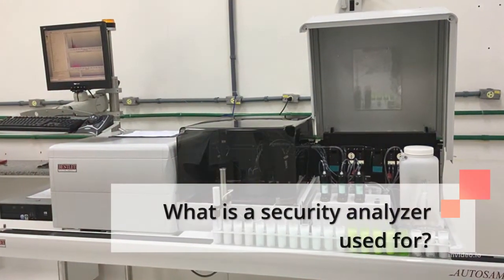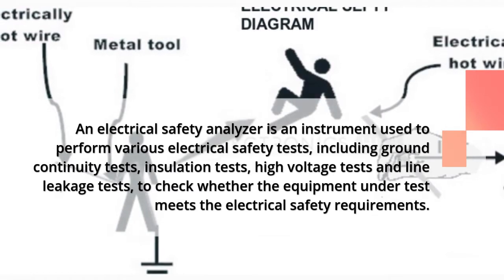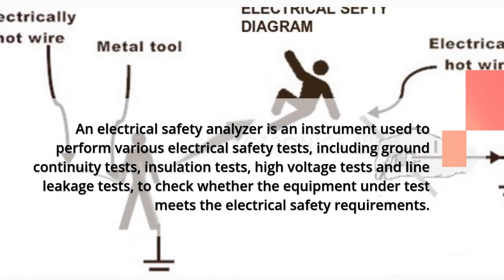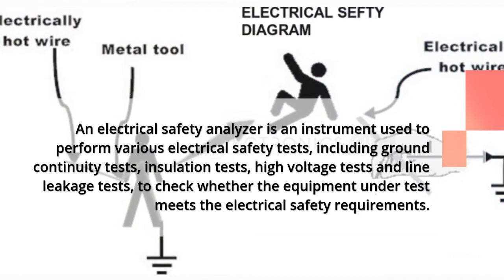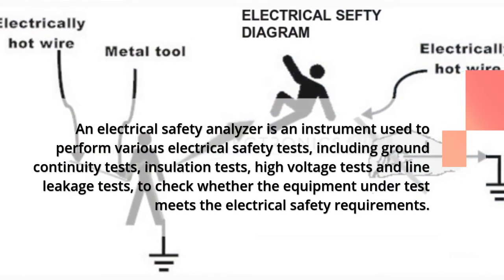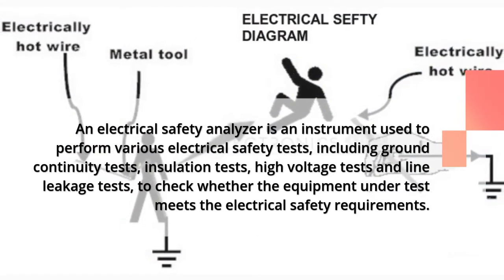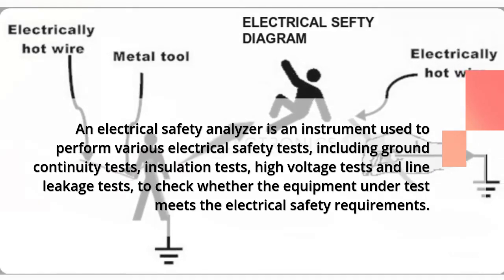What is a safety analyzer used for? An electrical safety analyzer is an instrument used to perform various electrical safety tests, including ground continuity tests, insulation tests, high voltage tests, and line leakage tests, to check whether the equipment under test meets the electrical safety requirements.